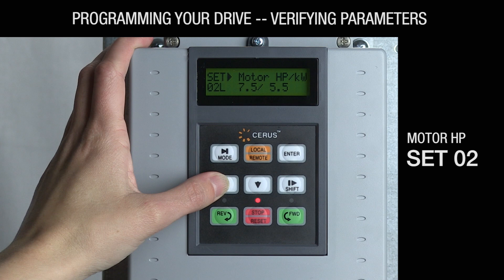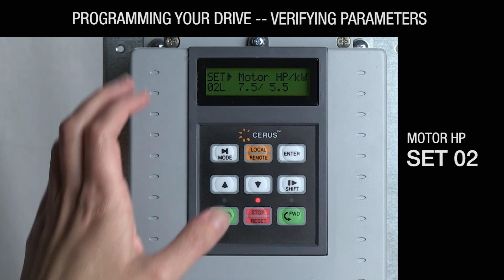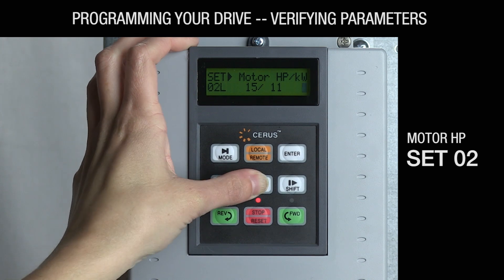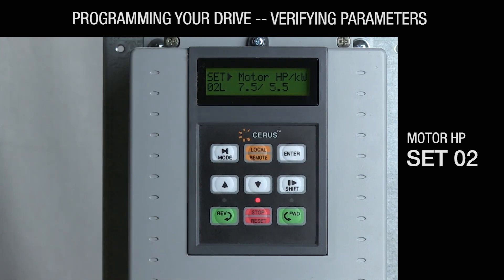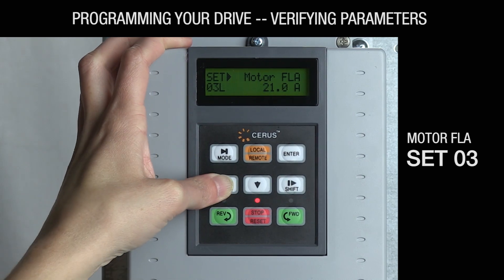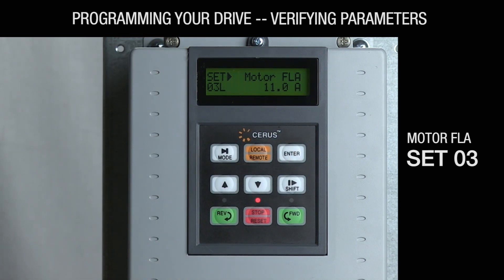SET-02: Motor horsepower should be set to the motor nameplate horsepower. Verify that it matches the horsepower rating on the motor nameplate. If it does not match, press the enter key so the flashing cursor appears, then use the up or down arrow key to adjust the value, and press enter to save this change. SET-03: Motor FLA is defaulted to a UL table value based on the horsepower and voltage indicated by your part number. Verify that this matches the full load amps. If it does not match, press the enter key so the flashing cursor appears, use the shift key to move the cursor to a specific digit, then use the up or down arrow key to adjust that digit as desired, and press enter to save.